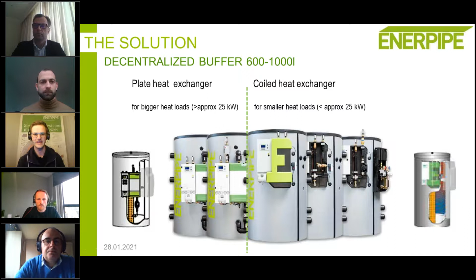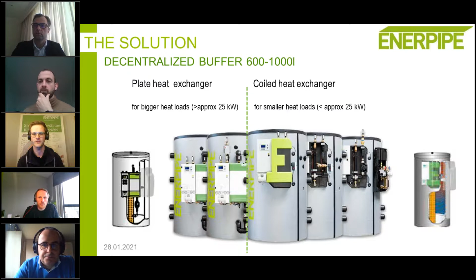So you're right, I haven't explained it in detail. For the original projects or the buffer tanks, already there was storage on the secondary side. So before we had a plate heat exchanger for the bigger houses, which you can see on the left-hand side, or a coil heat exchanger, but in this case it was both. The heat exchanger was before the buffer tank, so there was two times a heat exchanger: once to bring the heat into the buffer tank, and after that you had the heat exchanger for district heat, for the domestic hot water, with the freshwater station. This was also one aspect which we optimized in our new version.